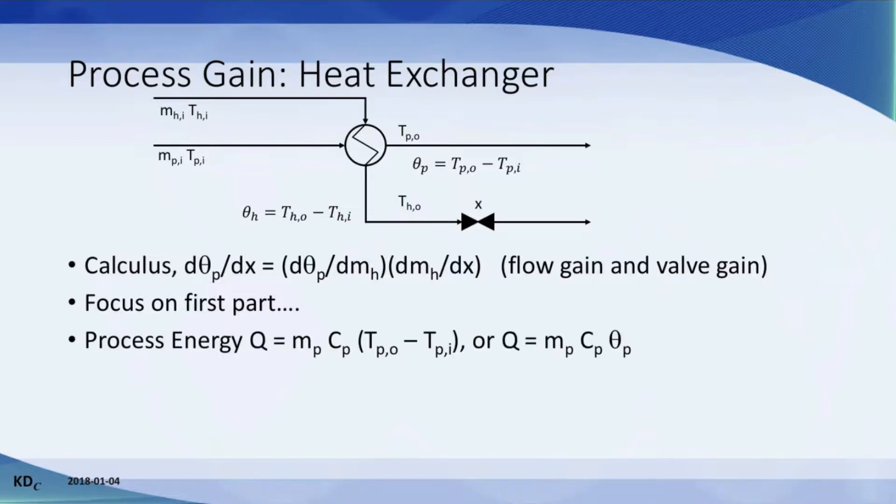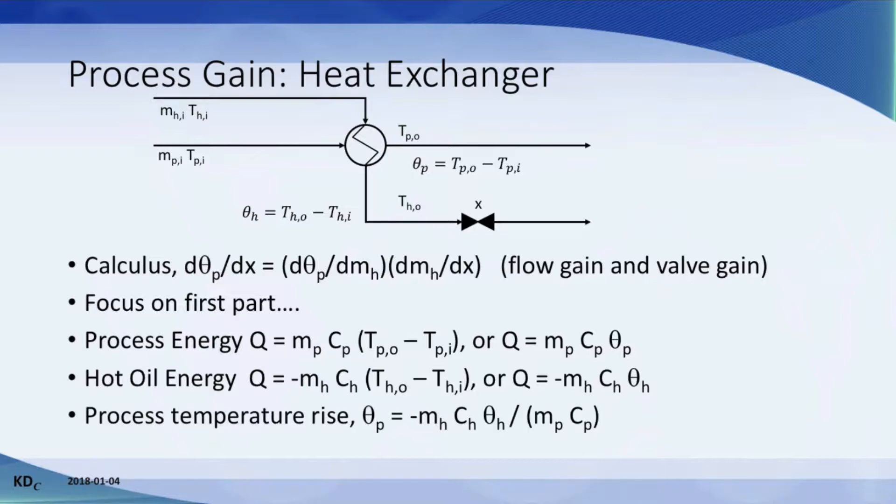The energy balance on the process side relates the process mass flow rate and temperature rise to the heat load q. The energy balance also applies to the hot oil side. We combine these to get an expression for the process temperature rise.